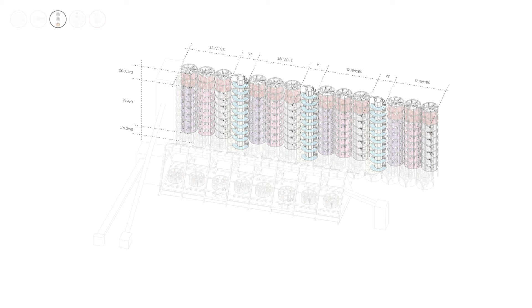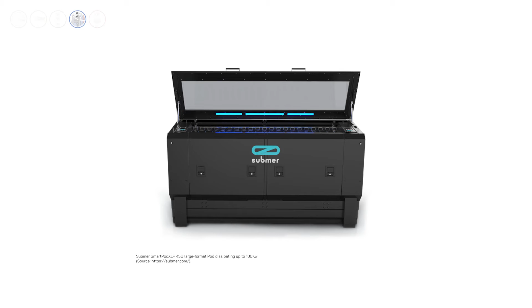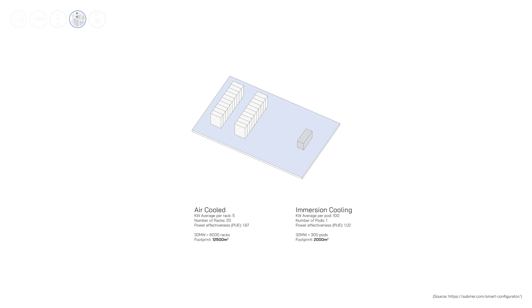The data center utilizes an immersive cooling strategy to reduce the overall footprint of equipment required as compared to a traditional data center arrangement. A traditional server arrangement would require 6,000 5-kilowatt racks to achieve a 30 megawatt data center. With the high-density arrangement possible with immersive cooling, this would be reduced to 300 immersive cooling modules. The immersion cooling data server is positioned on a raised access floor within the data center module.